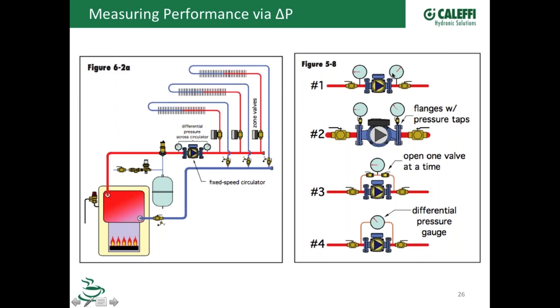One thing I'd caution you about is to make sure they're accurate gauges, number one, and that they're both at zero when you put them in there, so you get an accurate number, because sometimes you're only looking at maybe 3 or 4 or 5 pounds differential. So don't put an 80 or 100 pound gauge in here and expect to see a 1 or 2 pound difference. Get a gauge size close to what that pump is developing for pressure, and make sure that they're good gauges.